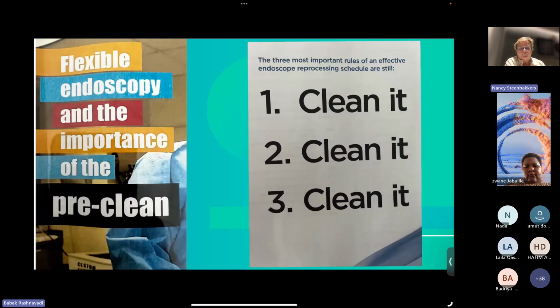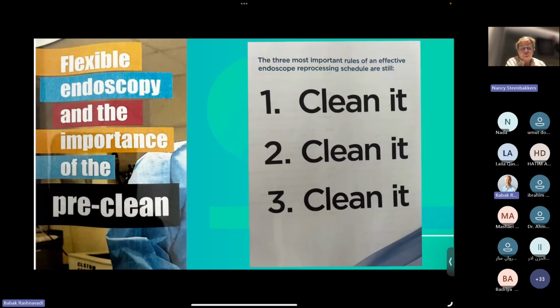Yes, please. Now, of course, as long as we cannot clean, you will never have a very safe endoscope. That's what you can see in all kinds of regulations, all kinds of manuals. It's always mentioned to clean, and to clean, and to clean your endoscope. The high-level disinfection is at a later stage, but the first thing is you have to clean it right after the examination with the bedside cleaning, and then it goes into pre-cleaning in a sink, and there you have to do a lot of steps, and it happens very often that the steps are not always followed. So please, next.